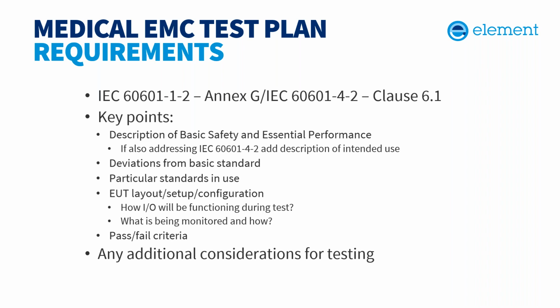Some of the key points are the description of the basic safety and essential performance. Those are the things you're supposed to be monitoring, that you're really focusing on during the -1-2 testing. What are they, and how are you going to make sure that they're being maintained? Similarly, for -4-2, if you're testing to that, you need to have a description of the intended use. You should include any particular standard. So, if it's a pulse oximeter, an infusion pump, whatever, you need to make sure that you're addressing any additional requirements in the particular standard.